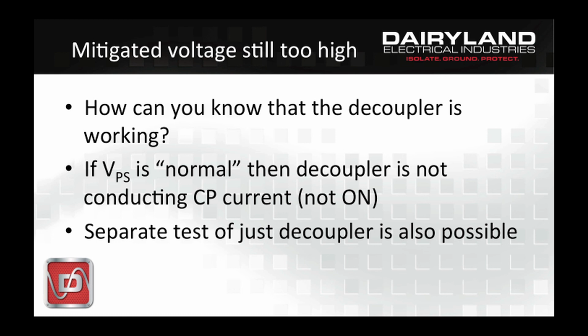If the decoupler were conducting or failed shorted, then it would affect the cathodic protection reading. The voltage would be collapsed. So any CP technician could take a pipe-to-soil reading and indirectly know if the decoupler is working. Normal, acceptable CP values represent a decoupler that is functional, because you definitely see it if the decoupler were conducting or shorted. As a comment, it is exceedingly rare for a decoupler to ever be failed, but if it does fail, it would fail shorted for safety. So you'd see that in the readings.